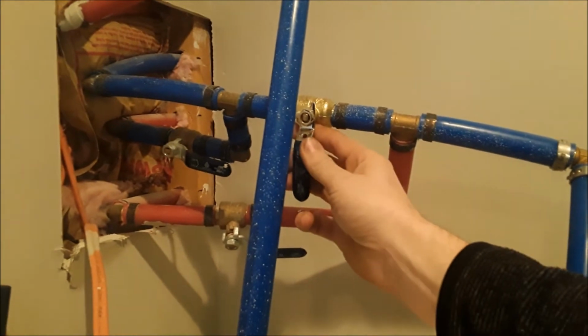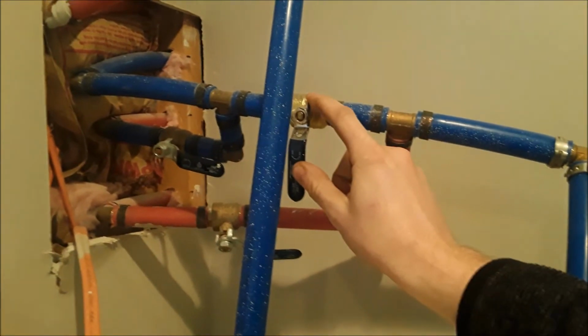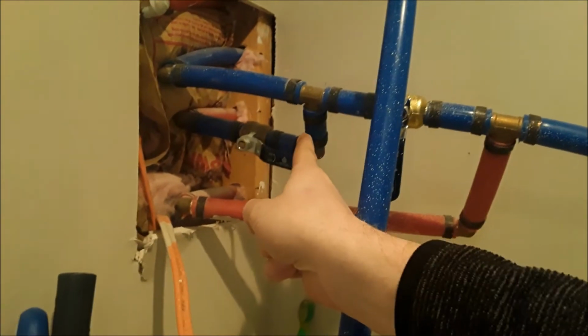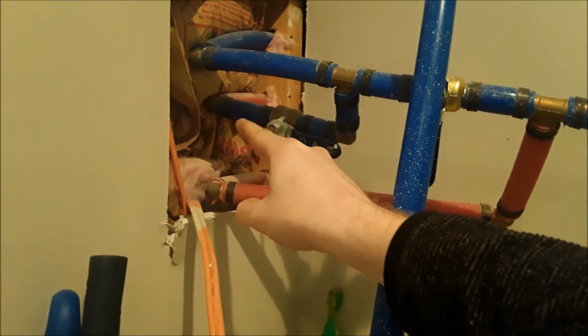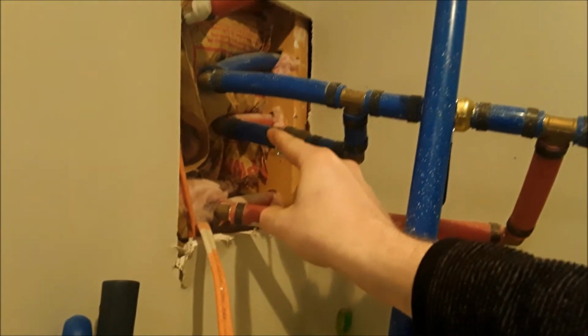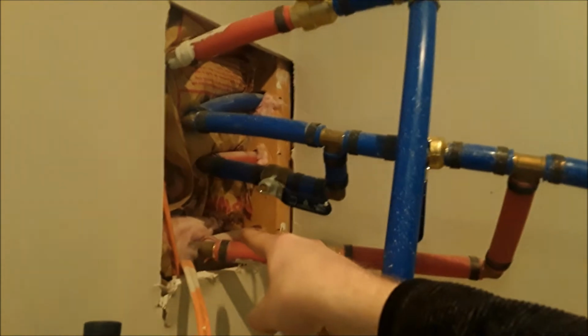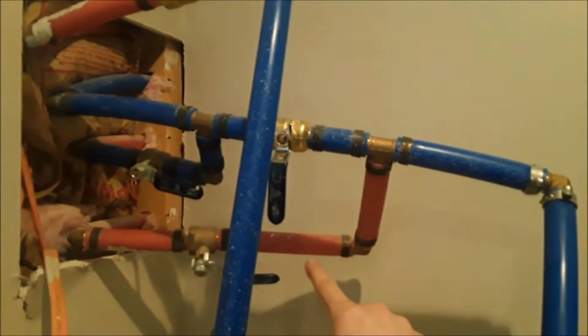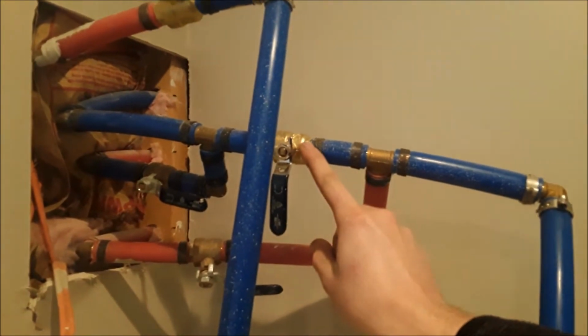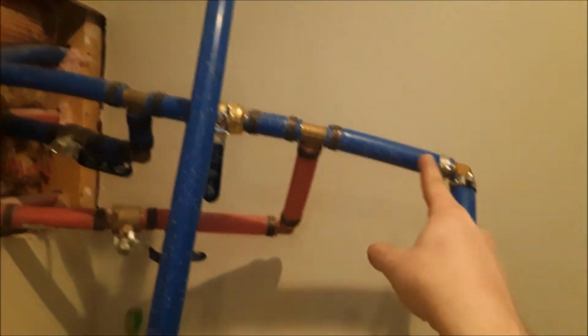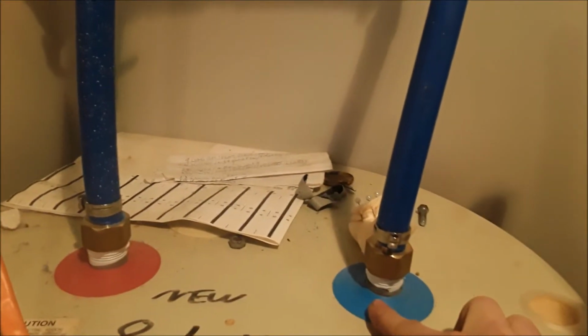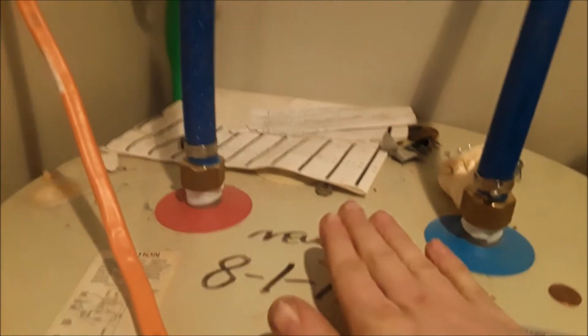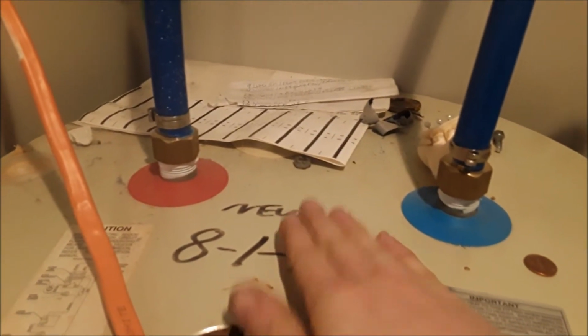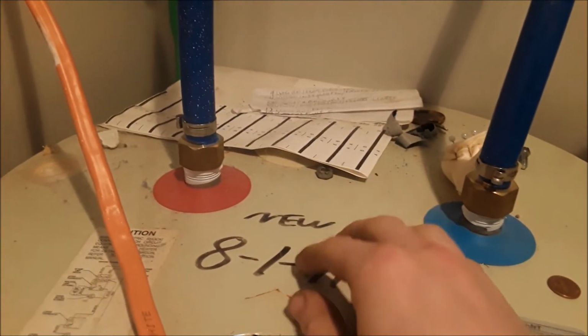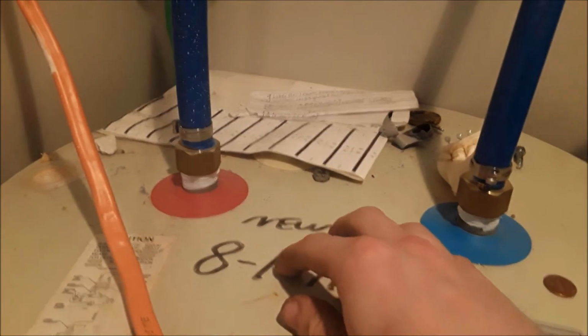You put a ball valve here, shut this ball valve off, and it sends cold water out towards your heater. Then your heater heats it up, brings it back in on this bottom line, and it comes in on this side of the shut off valve, and it puts preheated water into your hot water heater. And then this acts as just a storage tank, or if your heater goes out, then this will kick in and start heating as well.